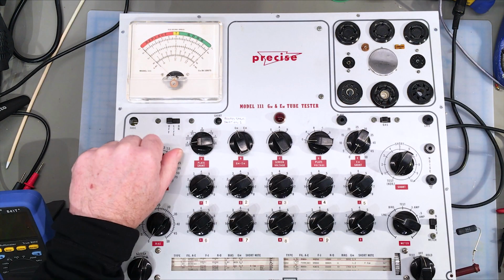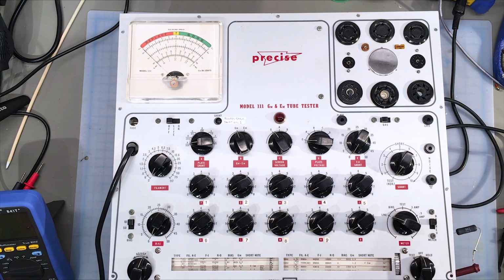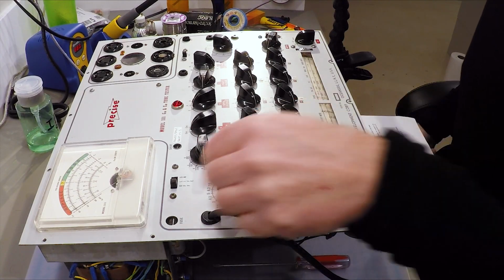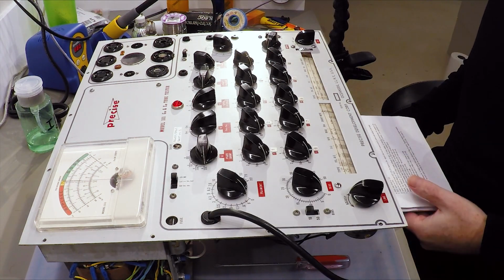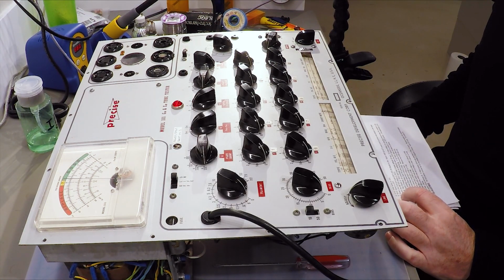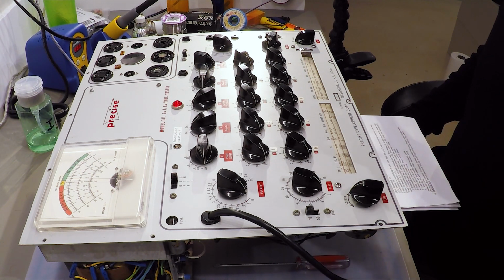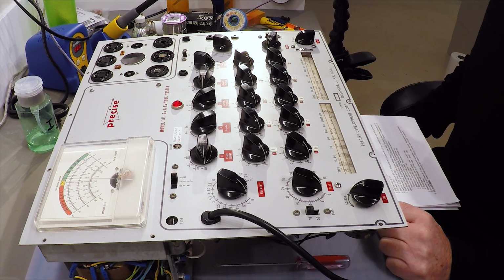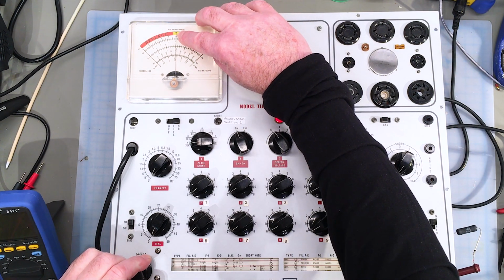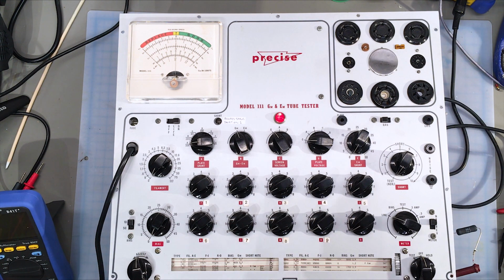So we turn all of the controls, A through O, to their full counterclockwise position. Filament bias counterclockwise, short to test normal, meter to line, and test to off. And then we can apply power to the instrument. And when we let it warm up, what we are to do is adjust the line so that we are in the center position. We'll just let it warm up for another few seconds here. And again, we're adjusting the line voltage so that we have the center position.